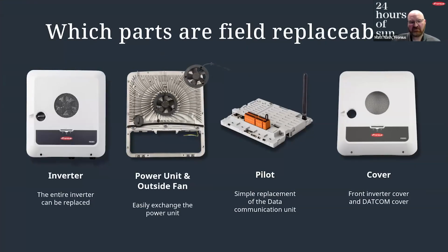In case you do need to do some field service on the inverter, these are the parts that can be field replaceable. So you can replace the entire inverter if necessary. However, this is very unlikely due to the fact that the inverter itself is essentially two parts. It is the power unit with the outside fan, or the pilot board, which is kind of the brain and communication board of the inverter. If necessary, you can replace covers and the connection area cover. But again, you really only have to worry about one or the other. It's very rare that you would need to replace the entire inverter.